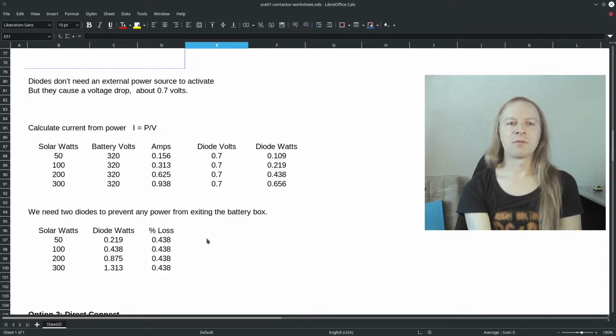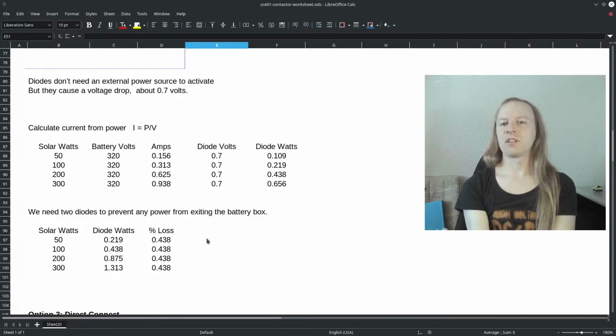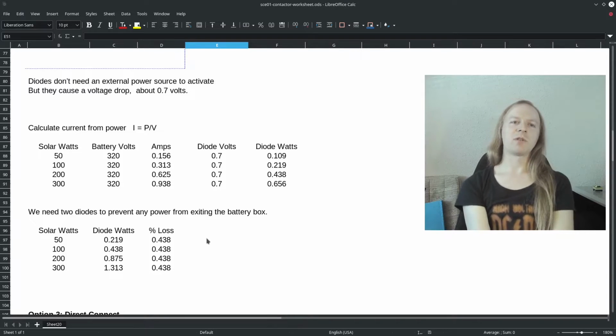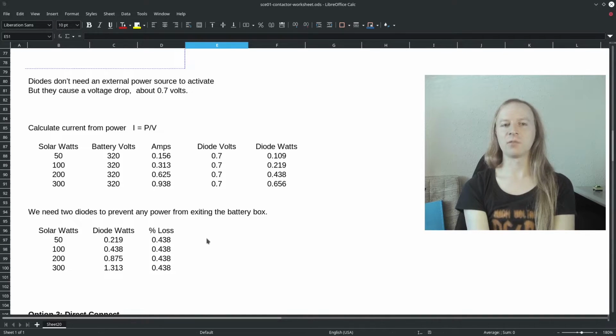So here we calculate a kind of worst case scenario: full power from the solar array, which is about 300 watts for our 420 watt array. To calculate worst case, we assume the battery voltage is at the very low end, almost completely depleted.